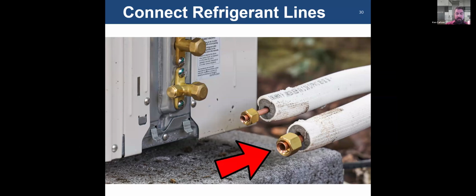But regardless of that, I spoke about a flare tool utilized for line sets, particularly copper. If you use a regular standard flaring tool that you buy from AutoZone or wherever, chances are when you flare this, it's going to split the copper. The flaring tools that you buy for refrigeration systems for line sets are concentric. So when they flare that fitting, they actually roll around the edge. It's much smoother. It prevents cracking, and it gives you the proper angle and proper fitting that you need. It's marked for the appropriate size so that you get the right size flare.